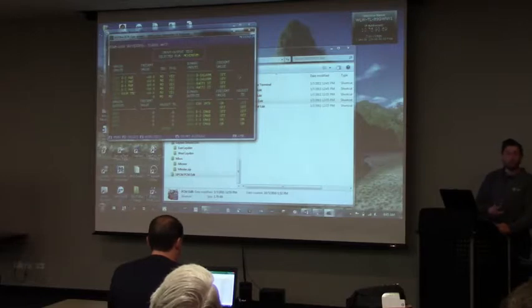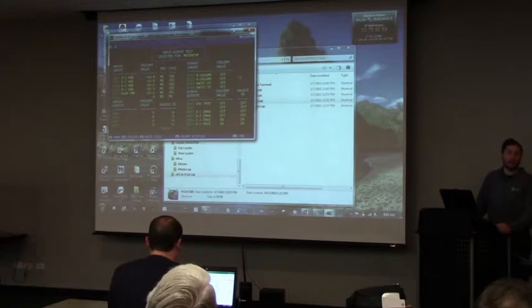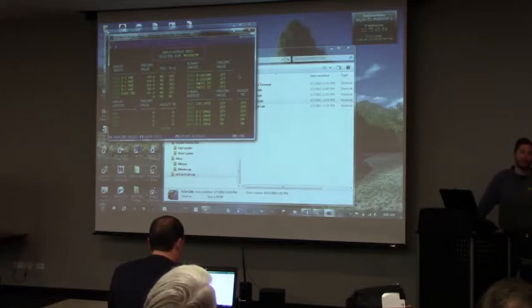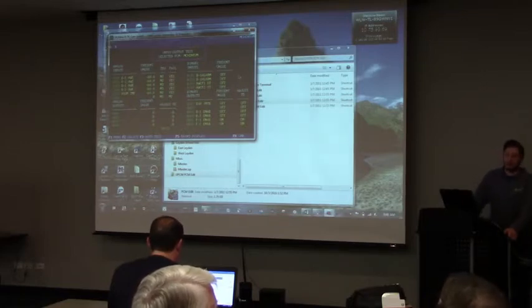Now, if you do that, does the programming start over from scratch, or does it go back to where it was before you started the test mode? It should be back to where it was. I don't have any issues where a program restarts, like if you start an exhaust fan or a supply fan, and you release it and put it in regular mode, it should still be running afterwards. I haven't had an experience where a supply fan turned off on me after I did all this. It doesn't carry its priority. It will wait for the routine that was running to go back. Okay. So it doesn't hold a priority in there and release it.